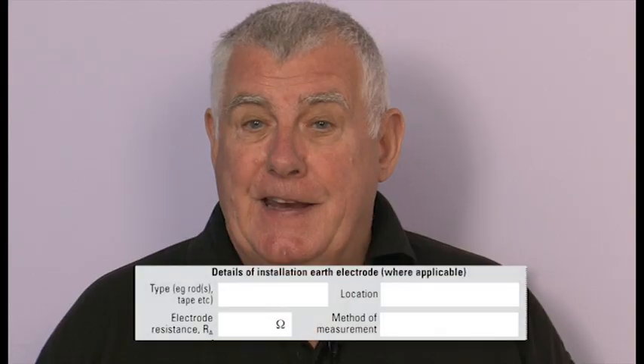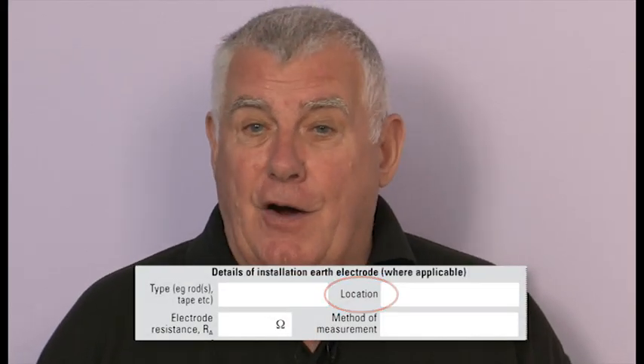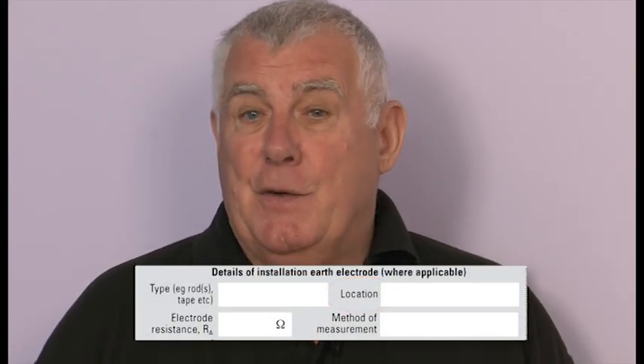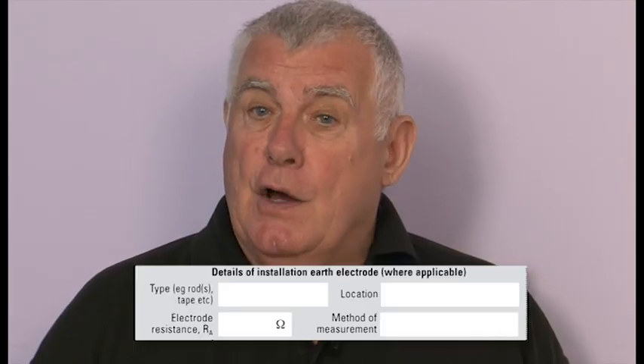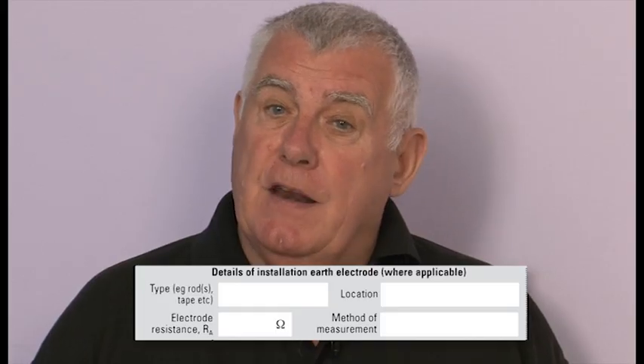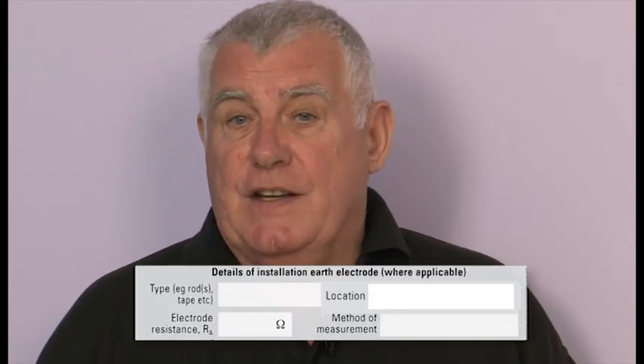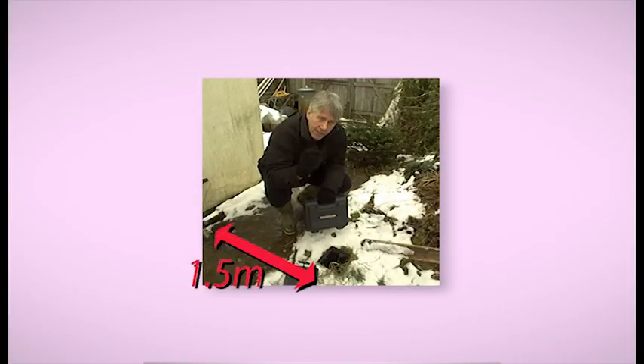Finally, for earth electrodes, we have location. Now I've seen this filled in with outside or in the ground, which isn't very helpful to the person who comes along for the next EICR. So it's better to write down a fixed point of reference. For example, 1 metre from the kitchen window, or as we can see in this picture, 1.5 metres from the side of the garage.